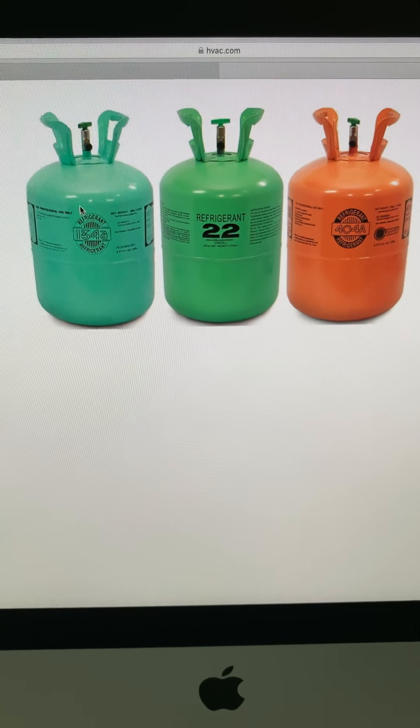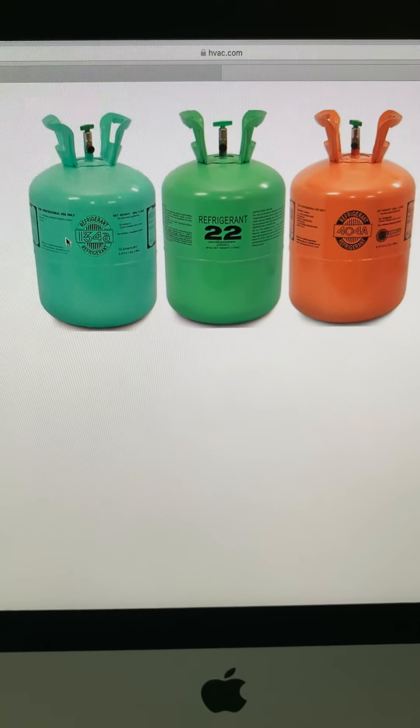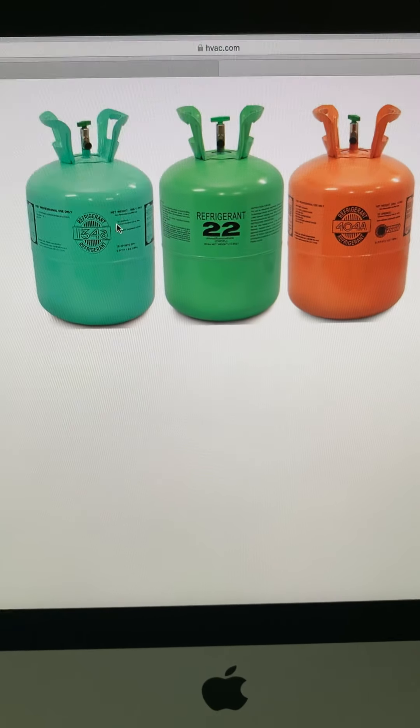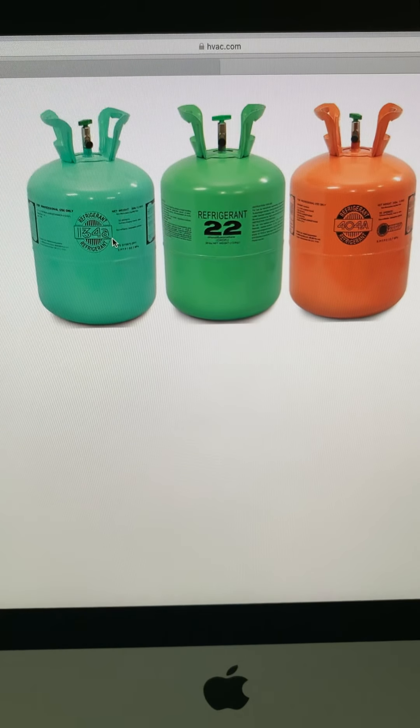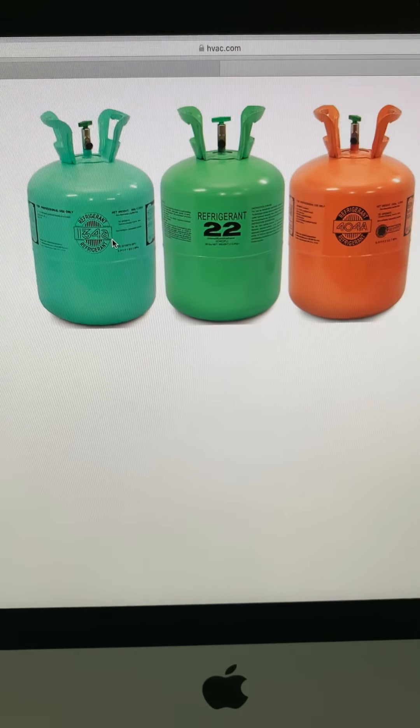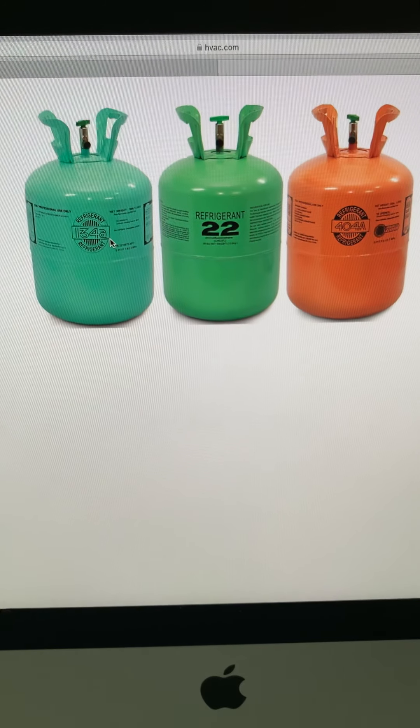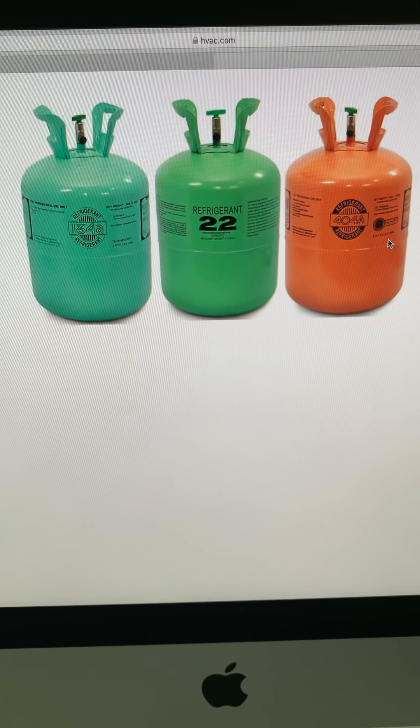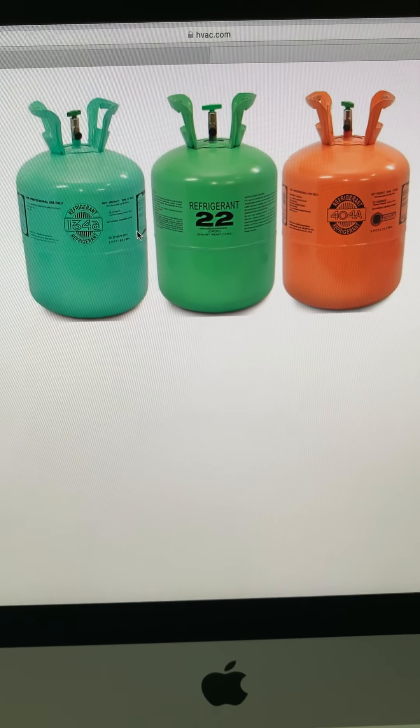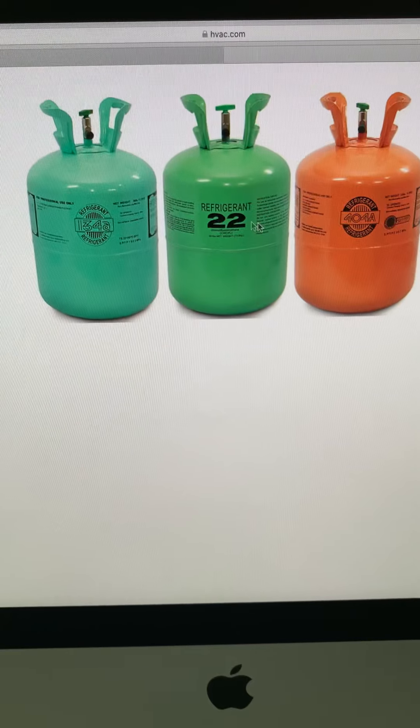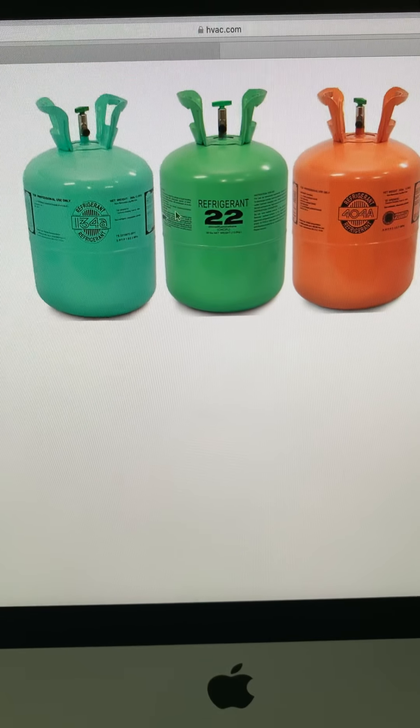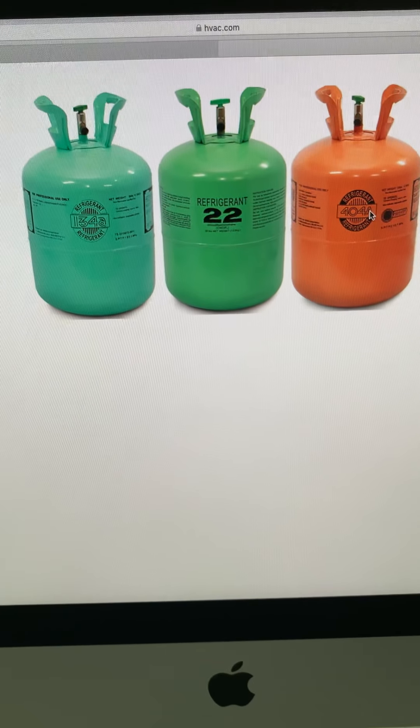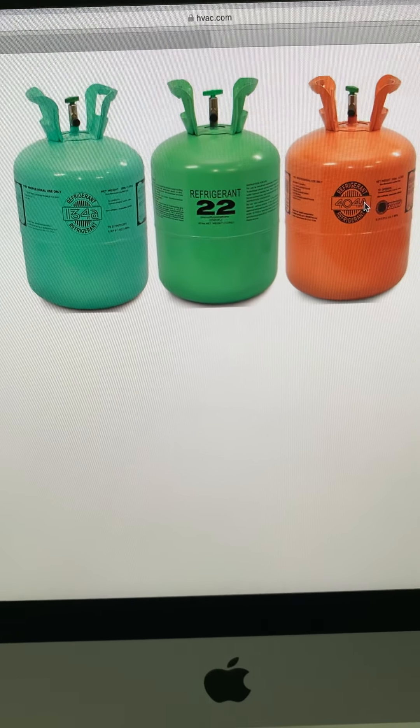You don't have that problem with 134A, but again, 134A is not going to work for frozen products like ice cream. So that's the difference between 134A and 404A. They require completely different units. The design of the unit is different.